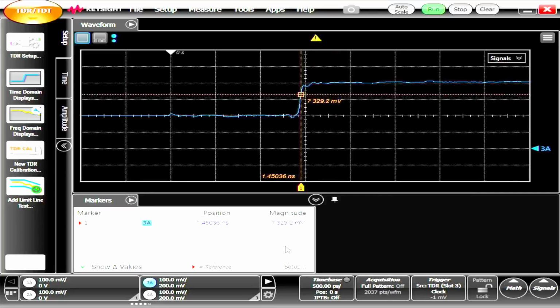Well, that was just a quick introduction to the cal standards and the methodology, and to show you the pain in the rear to calibrate this machine. But once you get it calibrated, it should hold values pretty well. I don't think it's going to drift off all that much. You really need to do it when you're doing a differential measurement where you care a lot. Otherwise, a lot of the TDR measurements are relative to one another, and you don't need to pay too much attention to it.